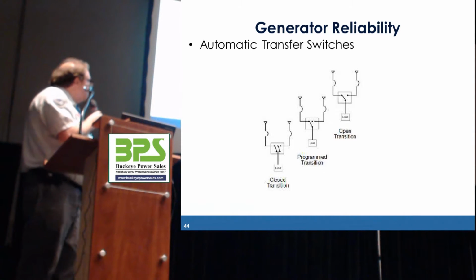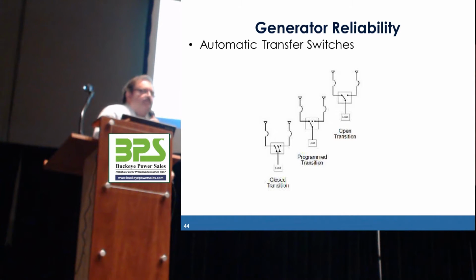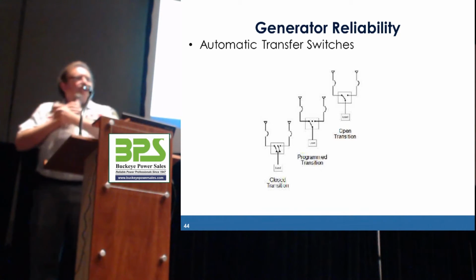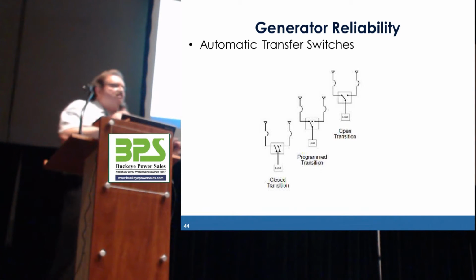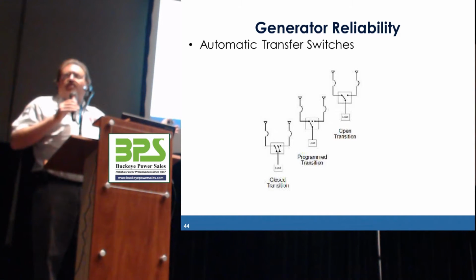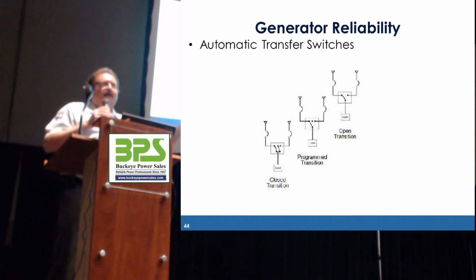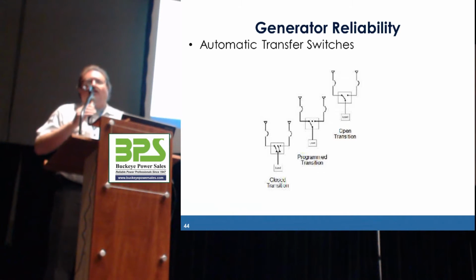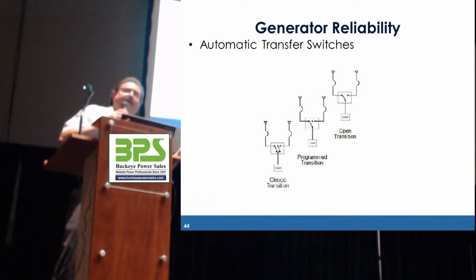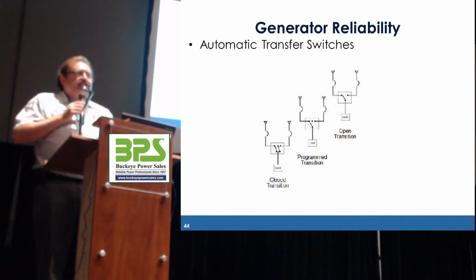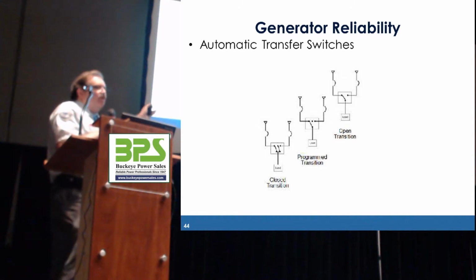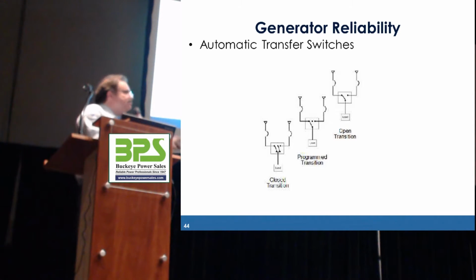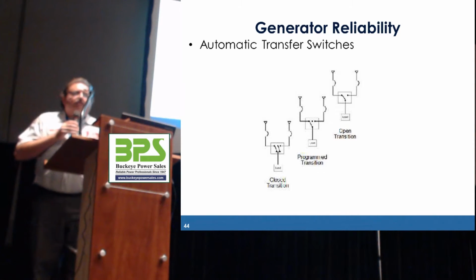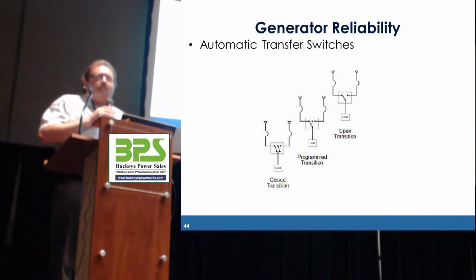And then there's what's known as closed transition transfer switches, which means we make to one source before we break from the other. Obviously, in a power failure situation, it's not going to make any difference. The power is going to fail. We're going to go over open. But when we come back, you can do it so that you don't see that transition. The closed transition makes it a whole lot easier to do that monthly test because you don't see any type of a bump.